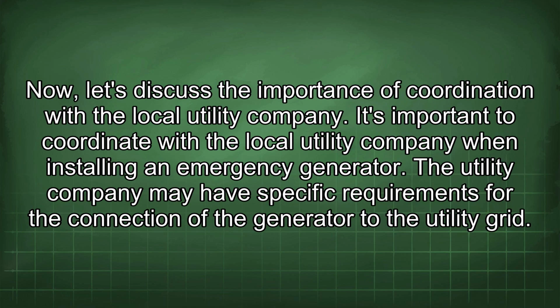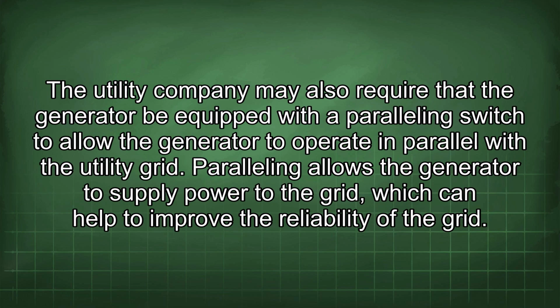Now, let's discuss the importance of coordination with the local utility company. It's important to coordinate with the local utility company when installing an emergency generator. The utility company may have specific requirements for the connection of the generator to the utility grid. The utility company may also require that the generator be equipped with a paralleling switch to allow the generator to operate in parallel with the utility grid.